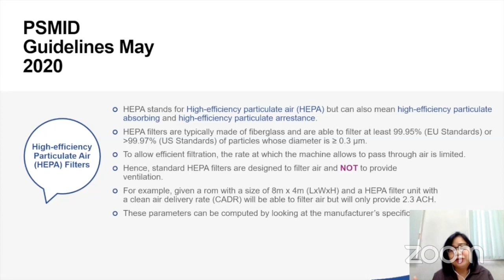There is now an available movable or portable negative pressure machine. So why do we say that this is very good equipment? It's expensive to set up negative pressure. So if you have a movable or portable negative pressure machine, that will guarantee you can generate negative pressure in each room, and you can move it from one room to the other depending on where you're going to use it. The currently available movable negative pressure machine actually has ULPA grade filters capable of filtering up to 0.125 micrometer. So this is very small, much smaller. And these are very low noise, so they will not interfere with the OR environment.